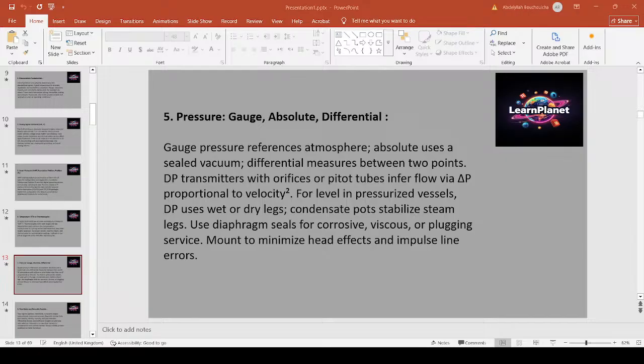Gauge pressure reads relative to atmospheric pressure, good for process tanks. Absolute pressure is needed for vacuum or when barometric variations matter. Differential transmitters measure delta P between two points, used for flow, filter monitoring, and level in pressurized vessels. In steam service, use condensate pots, sealed wet legs, or dry legs to avoid false readings. For corrosive fluids, use diaphragm seals, slope impulse lines to avoid traps, and ensure proper drain and venting.